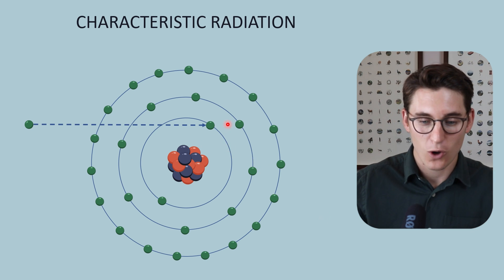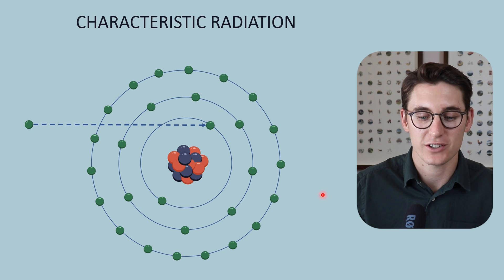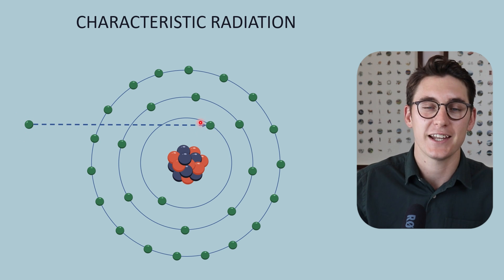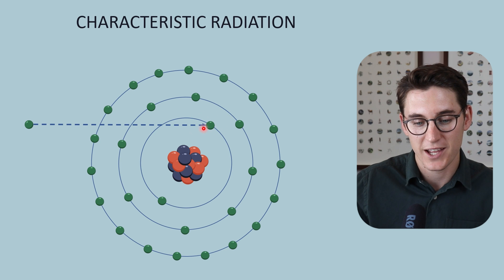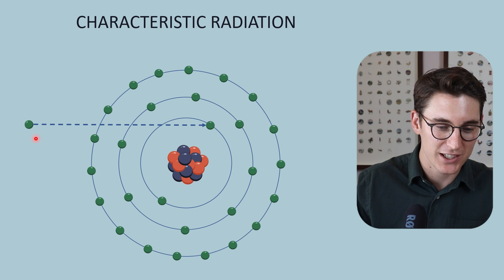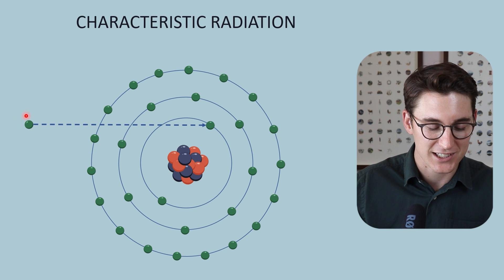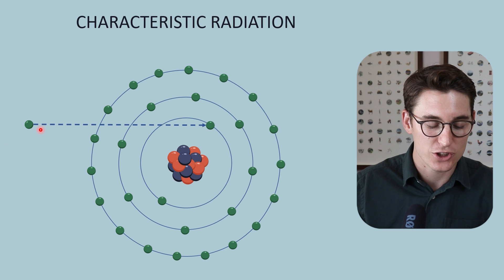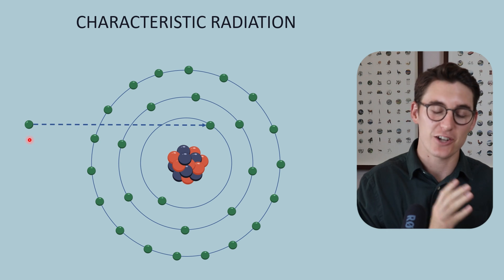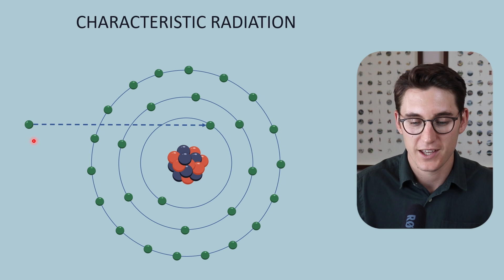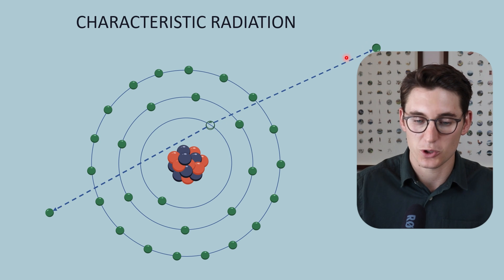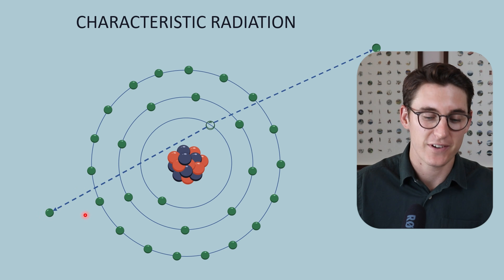This accelerating electron will collide with an inner shell electron of our target material, and if the kinetic energy of this electron is higher than the binding energy of this k-shell electron, then that k-shell electron will be ejected from our target. This occurs only if the energy is higher than the binding energy, which is determined by our tube potential — the kVp — the differential between the cathode and our anode that has accelerated this electron. If that energy is higher than the binding energy, we get the release of that k-shell electron, known as a photoelectron, and this striking electron is deflected off at an angle.